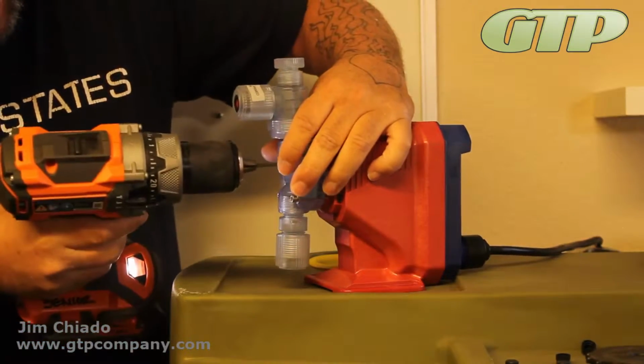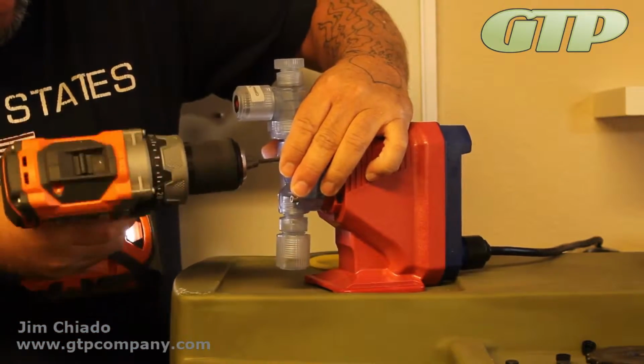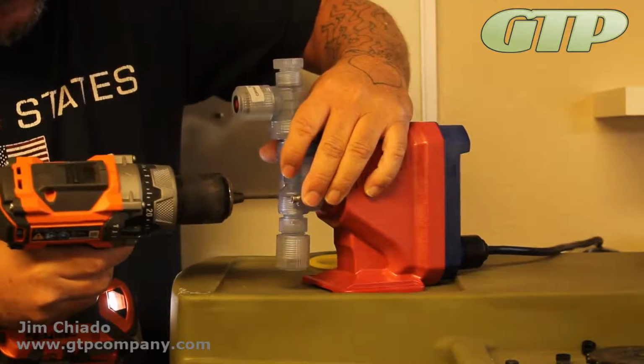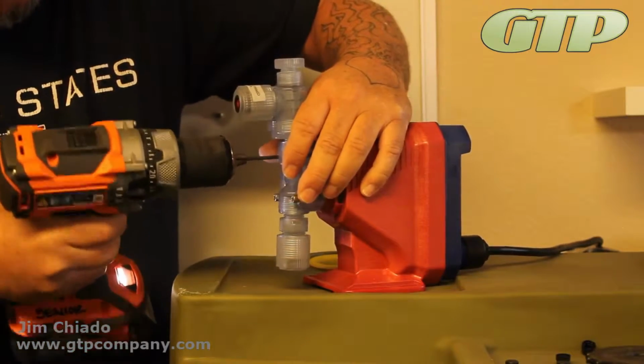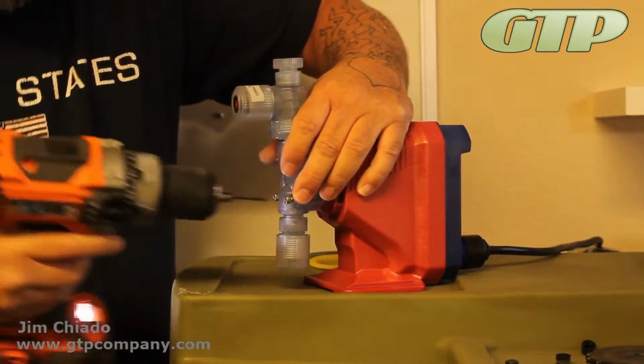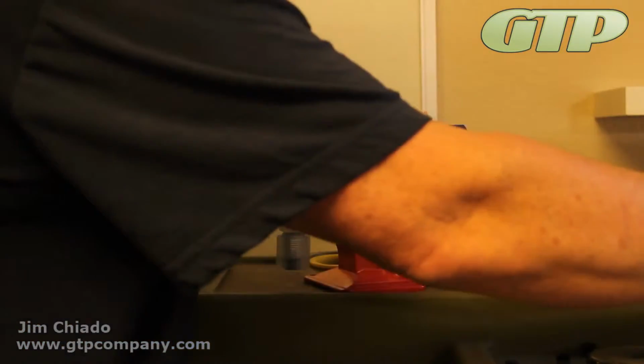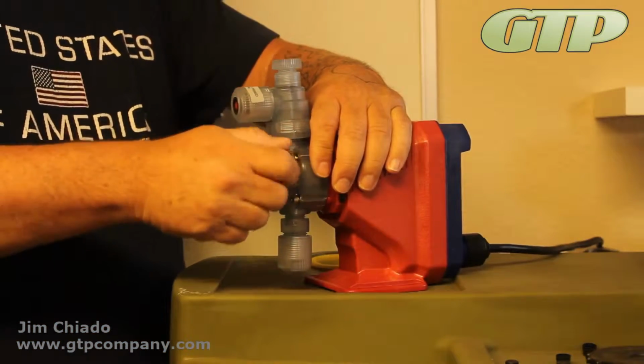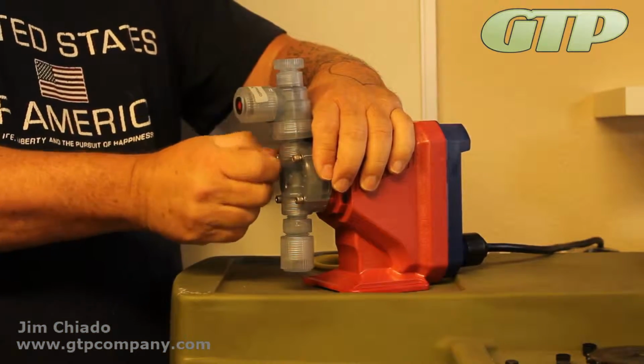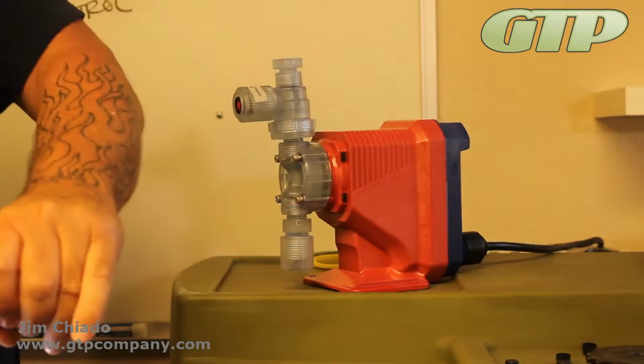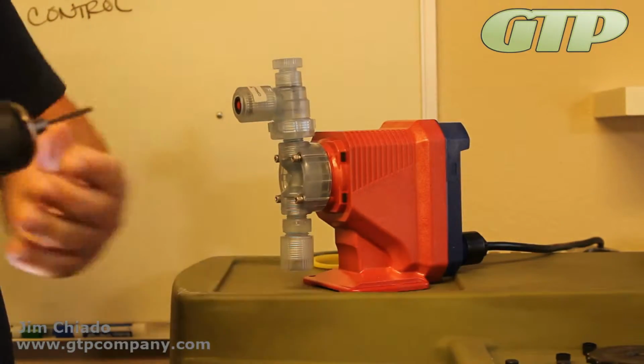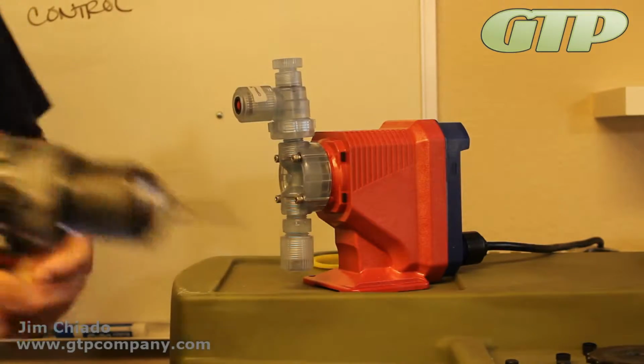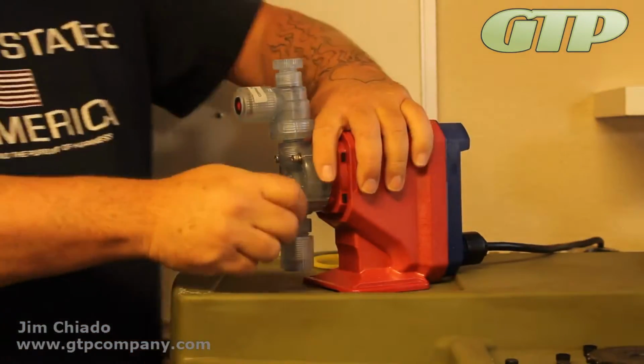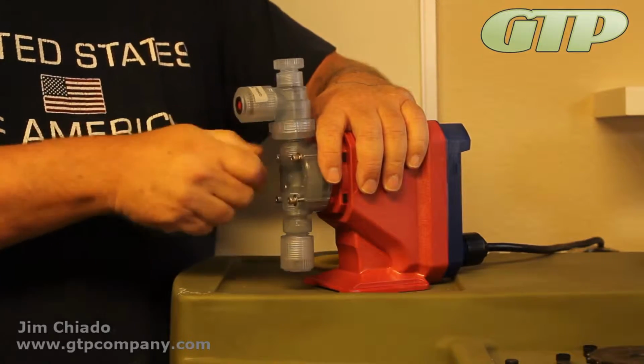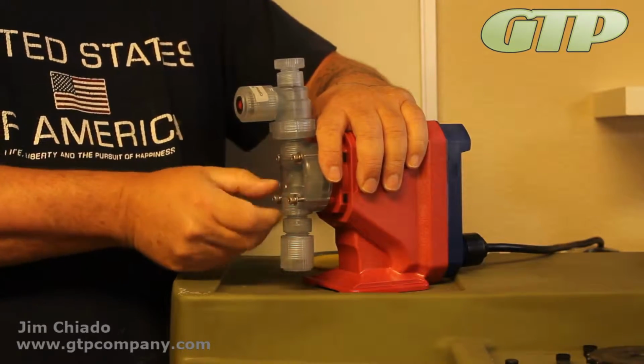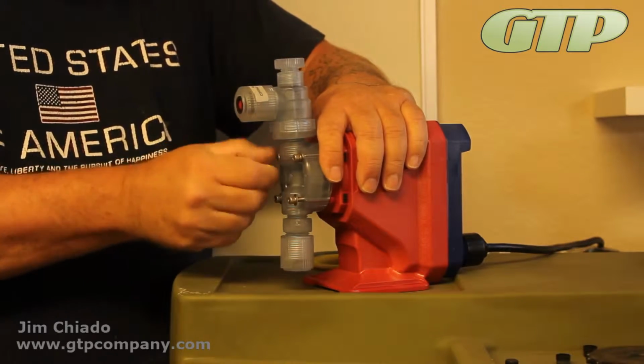Now, the factory may not like seeing me do this, but you can over-tighten and under-tighten the pump, especially with a drill head like that. I do take precautions with mine, and I have it set so that it basically doesn't over-tighten for me. I turned it all the way down to 1 just so it won't do that on me. A lot of guys will over-tighten and break the pump head, and that's not that hard, it's just a piece of plastic.